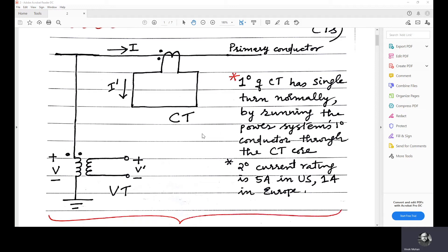Now, coming to the primary circuit. Primary circuit has a small number of turns in CT. The primary circuit has a large number of turns in PT or the voltage transformer. The secondary circuit has a large number of turns and cannot be open-circuited in a current transformer. And the secondary circuit of a potential transformer has a small number of turns and can be open-circuited.